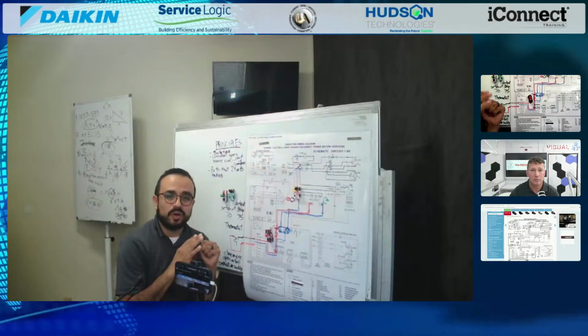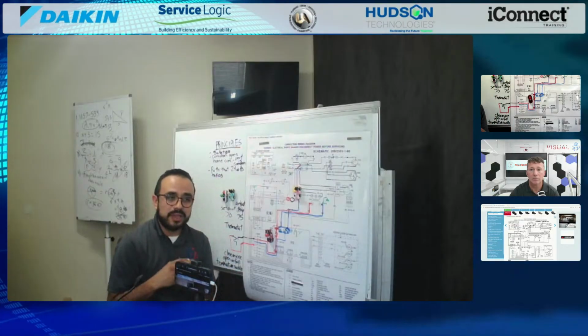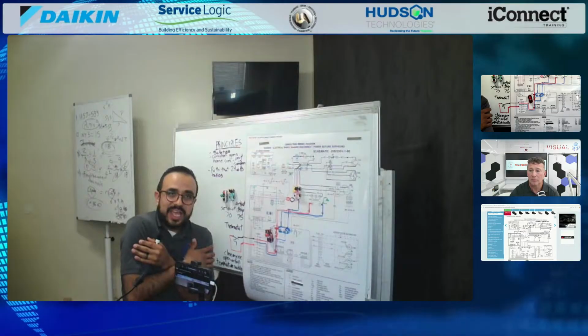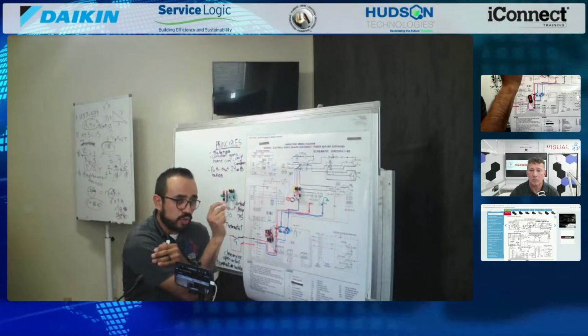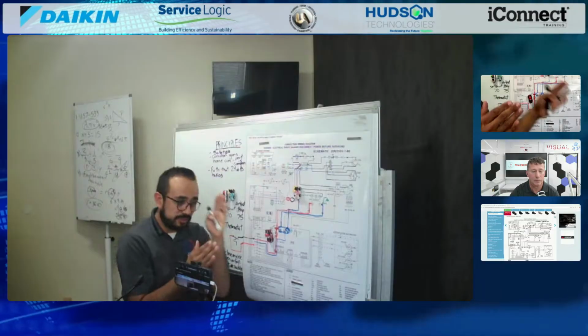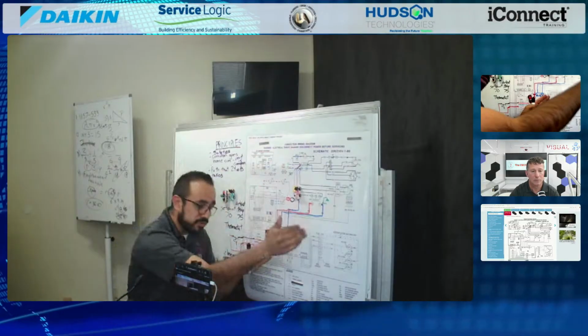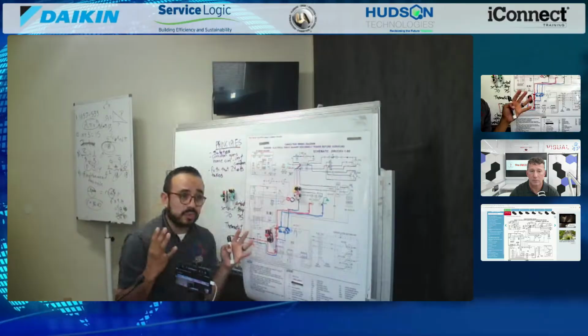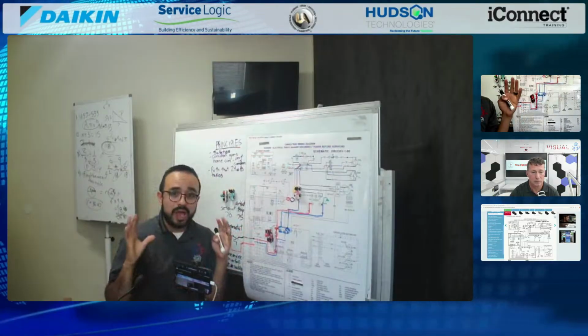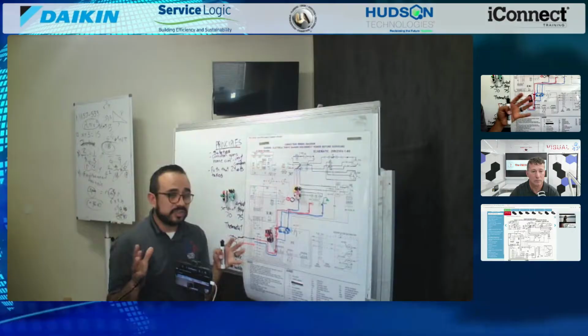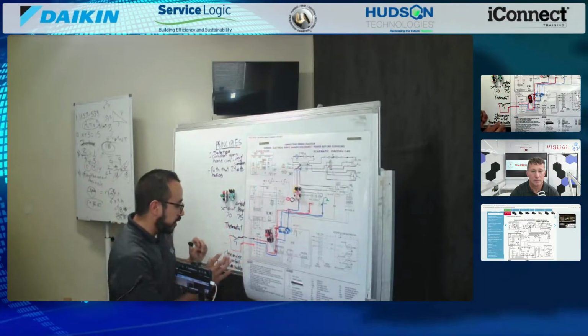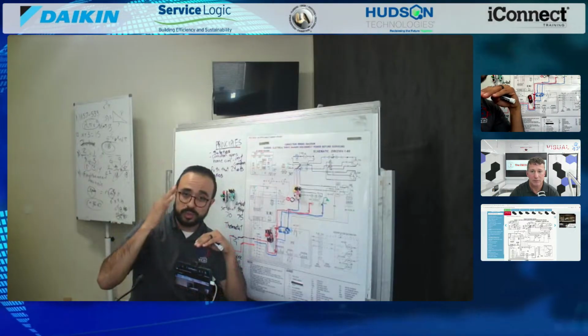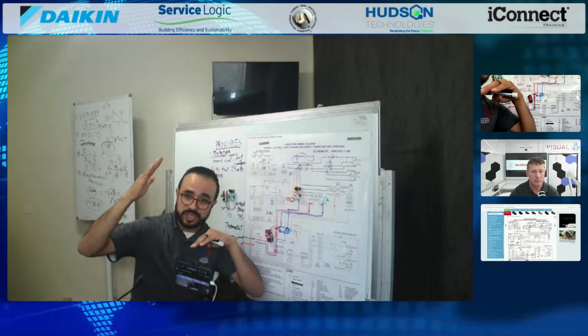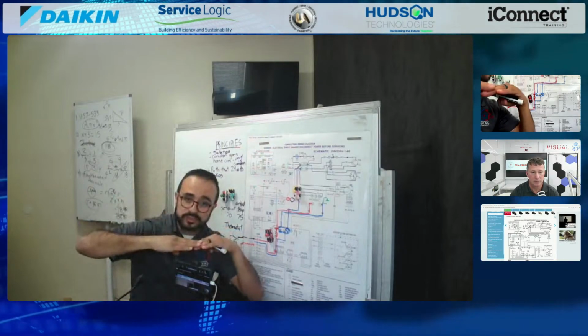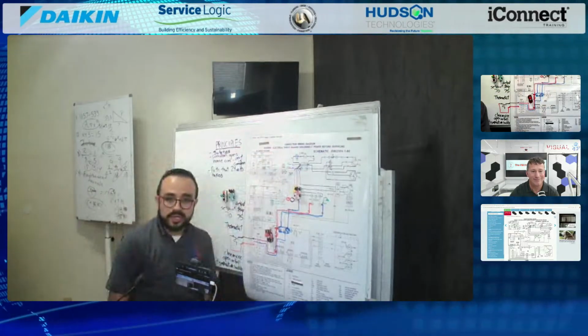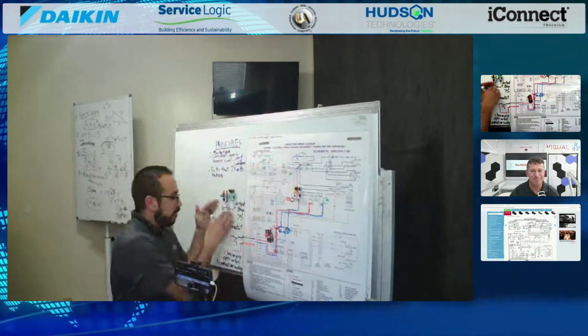Going back to the switch function, if it's really hot and I have the mode on cool, and the set point is 70, and it goes over 70 to 75 degrees, the thermostat's telling me, hey, I want a call for cooling, because this thermostat, at least with Y specifically, it's close on rise. So what that means is temperature rises over the set point, the bridge closes. So then current can go through, right? So that's the whole concept. This is a switch.